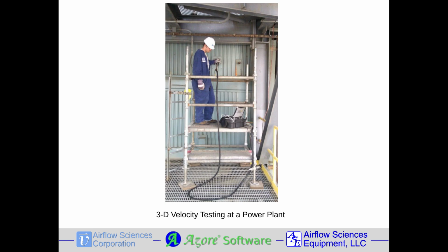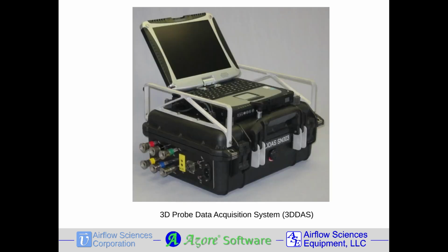While the S probe requires only a single pressure as well as a temperature to be measured at each point, which can easily be done with a single handheld meter, the 3D probe requires 3 separate pressure measurements, plus an angle measurement and a temperature measurement. This results in a much more complicated setup to haul around a plant, as well as much greater opportunity for error when recording all that data.